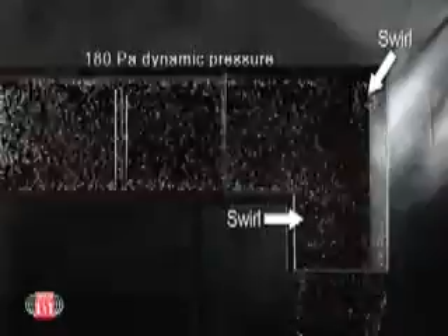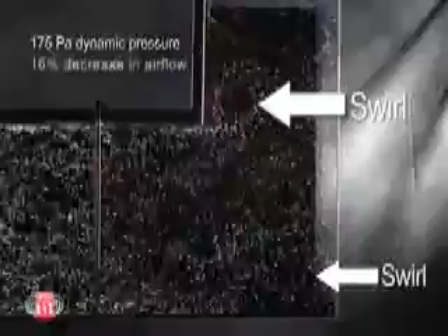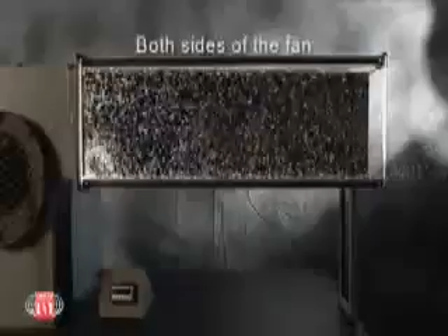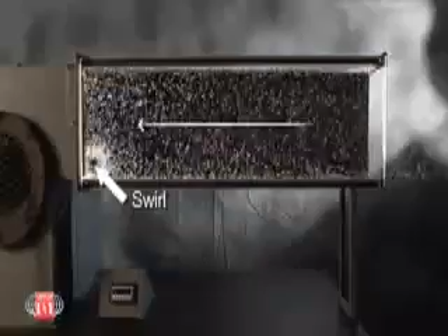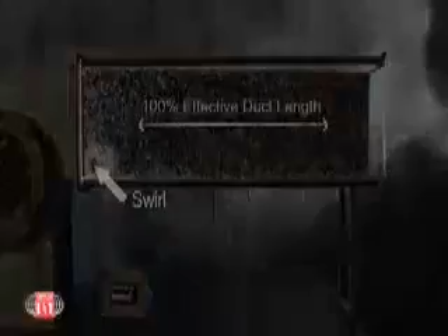However, if we change the direction of the elbow to opposite that of the fan's rotation, we reduce it even more to 175 pascals dynamic pressure, which is a 16% decrease in airflow. So major ducting inefficiencies can occur on both sides of the fan. One must also remember that a major additional factor is the length of the ductwork itself. You should always strive to achieve 100% effective duct length.